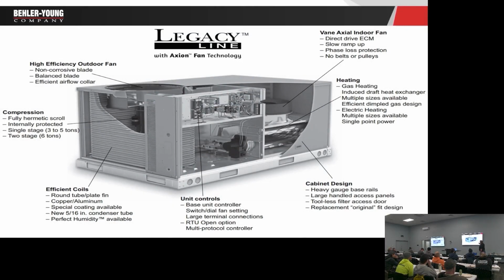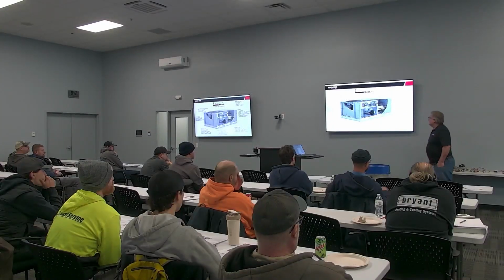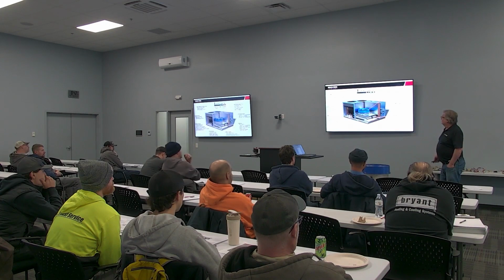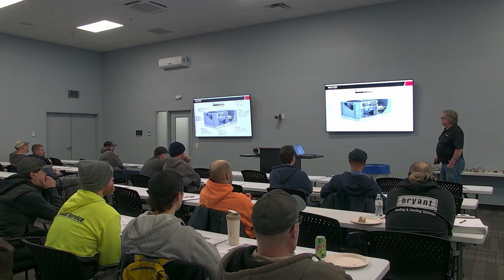Okay, some of the other changes when they converted to this. We got rid of the belt drive. We went to the single ECM motor. We've gone to a TXV. All right, so they've eliminated those flow check, those AccuCheck valves. Is everybody familiar with those? We used to have little orifices in the header. All right, we got rid of those. They've gone to all TXVs now. So that was one of the other big changes on this, besides going to the blower motor. Okay. I'm sorry, that's the 3 through 5 ton.